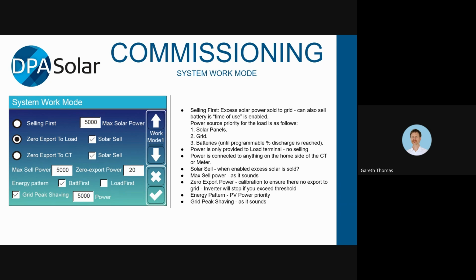So it will provide power out through the grid connection of the inverter, but at the point where the CT is, it's going to try and keep that to be zero. So if you have some loads in between the CT and the inverter, say they're drawing 500 watts, it will allow 500 watts to go through to the grid connection of the inverter, but they're going to go straight into the loads, so the current value that the CT is seeing is zero. So it's going to try and keep that to zero. This is how most export limitation devices work for inverters.